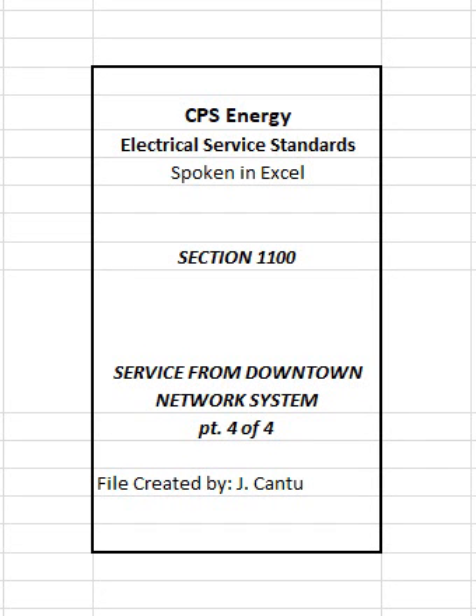1103 Customer-owned service disconnecting means. Customer-owned service disconnecting means shall be provided with an overcurrent device that shall be an integral part of the service disconnecting means and/or shall be located immediately adjacent thereto. In addition, the customer service disconnecting means shall meet the provisions outlined in A and B below.